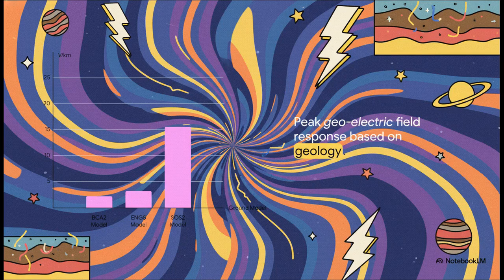Let's see how this builds. This threat actually compounds when we look at how the ground itself reacts. If a massive 2,400 nanotesla per minute electrojet event hits, some regions, like the BCA2 geology, only see a 2.2 volts per kilometer field. But look at the SDS2 region: it absorbs a massive 15.6 volts per kilometer hit. Depending entirely on the dirt beneath your local substation, the invisible threat from space is magnified nearly 7 times over.